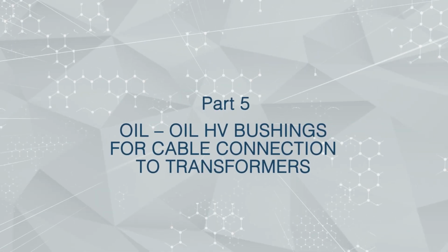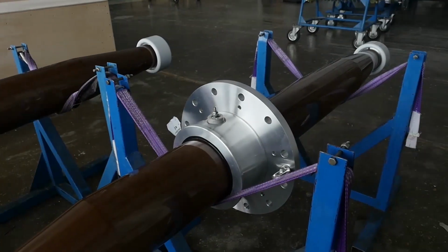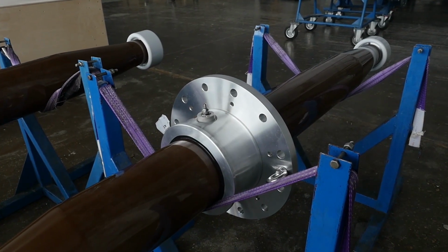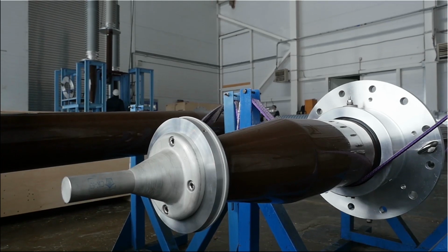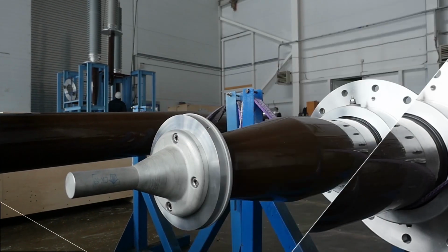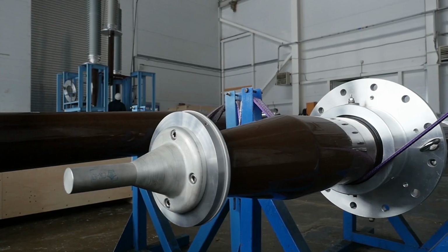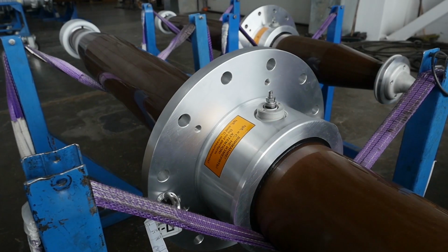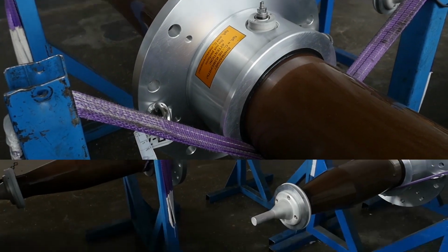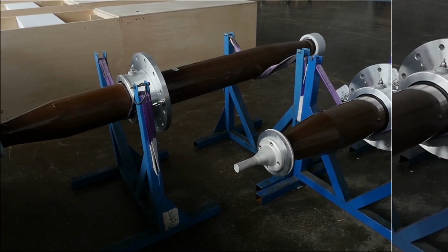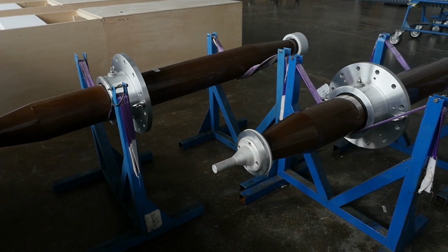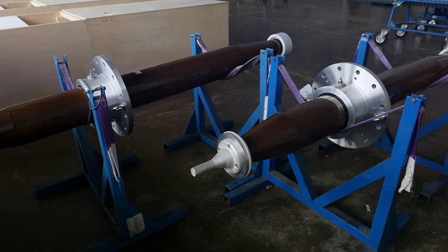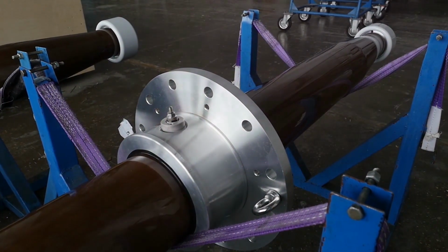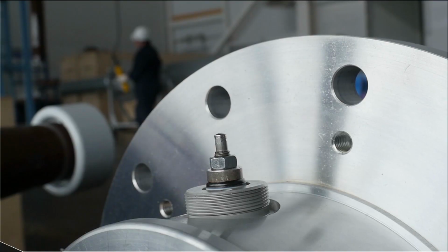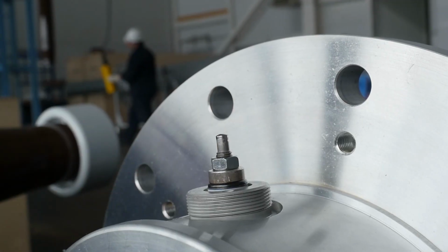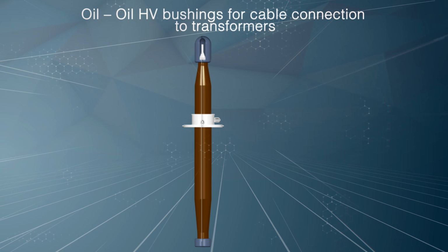Oil-to-oil high-voltage bushings for cable connection to transformers. The bushing is a feed-through insulator intended for connecting a transformer tap with the cable and sleeve. During operation, the bottom part of the bushing is inside the transformer tank, while the upper one is in the cover of the cable gland. Both parts of the bushing are immersed in transformer oil. Therefore, such bushings are called oil-to-oil.